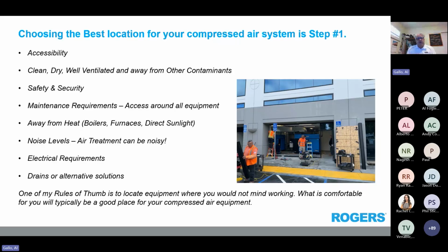We also want to make sure we put it in a clean, dry, well ventilated area away from other contaminants. I'm using an example of a cement plant: we don't want to put the compressed air equipment right in the dustiest part of a cement plant. So just keep those kinds of things in mind. Also, safety and security is a big one to keep in mind as well. Does it need to be locked down? Is it okay if people go in and start messing with it? And especially with a heated desiccant dryer, those vessels get very hot. We don't want people touching them.